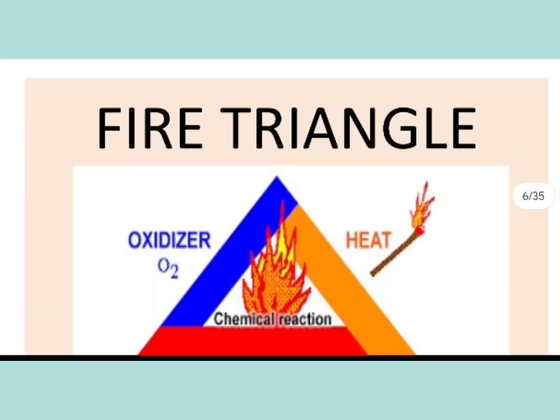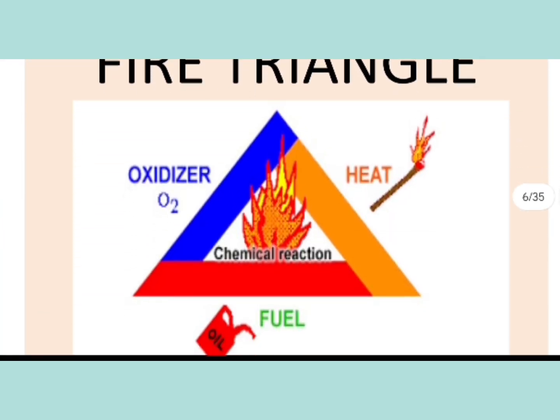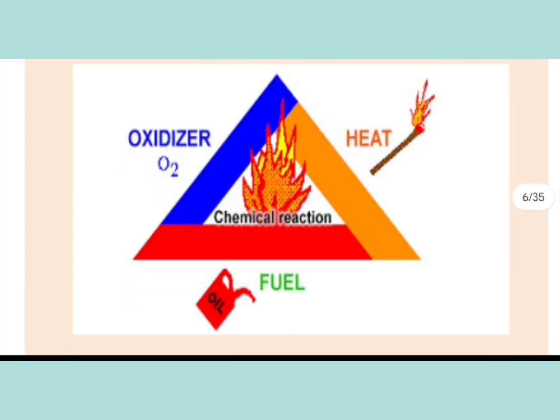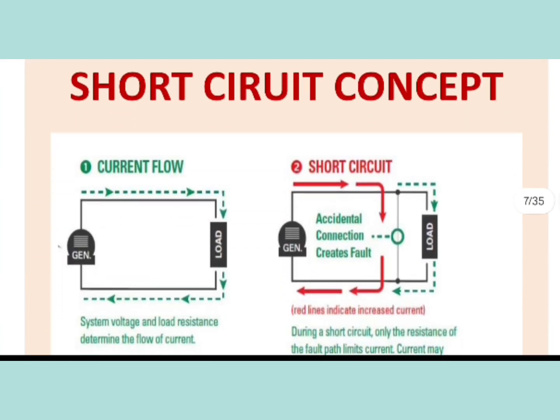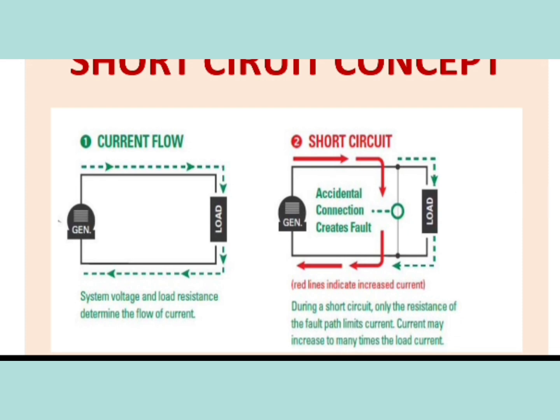When your tripping systems, your protection systems fail, such accidents happen. And when I say fire, you have to understand the three components: you need oxygen, you need heat, you need fuel. The fuel is the combustible material, oxygen is the oxygen available in the atmosphere, and the heat is the heating effect of current because of a short circuit. Time to understand what a short circuit is. In a short circuit, the intended path of the current flowing through your gadget becomes short circuited. That means there is some failure of insulation, and the current does not follow the intended path and goes back to the source through earth, taking a shortcut path, as depicted by that picture.